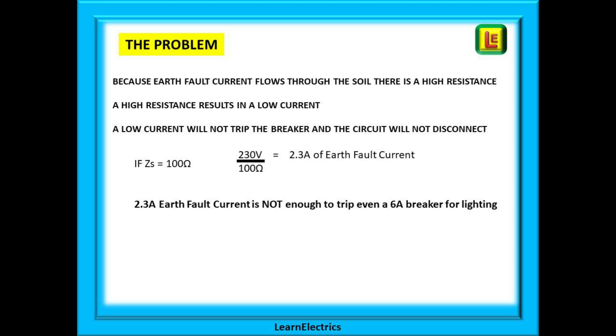So what is the problem with the TT arrangement? It's very easy. Because earth fault current flows through the soil, there is a high resistance. A high resistance results in a low current, and a low current will not trip the breaker and the circuit will not disconnect. You can see from the calculation that if the soil resistance was 100 ohms, then only 2.3 amps of earth fault current will flow, and this is clearly not enough to cause even a 6 amp breaker on a lighting circuit to trip.